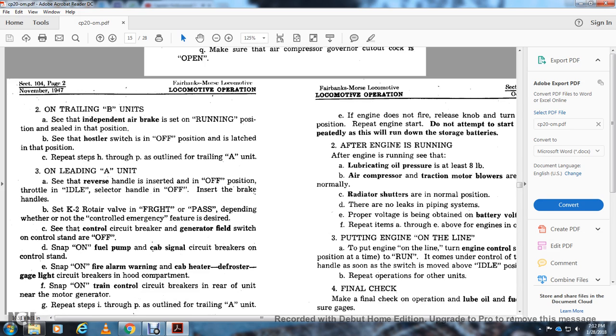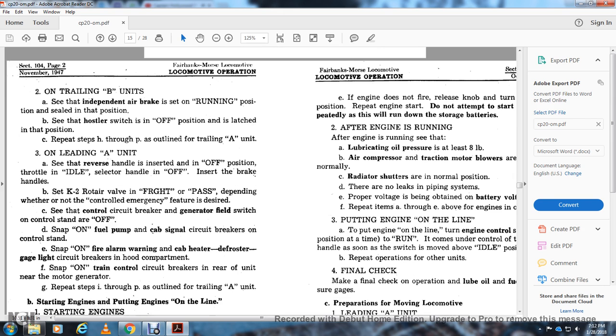For the control circuit breaker with the generator field switch on control stand are off, then snap on the fuel pump. With the cab signal circuit breaker on the control stand, snap on the fire alarm to warning, cab heater, defroster gauge light circuit breaker on the hood compartment, snap on the train control circuit breaker on the rear unit with the motor generators. Repeat steps I through P of the outline on trailing unit A.